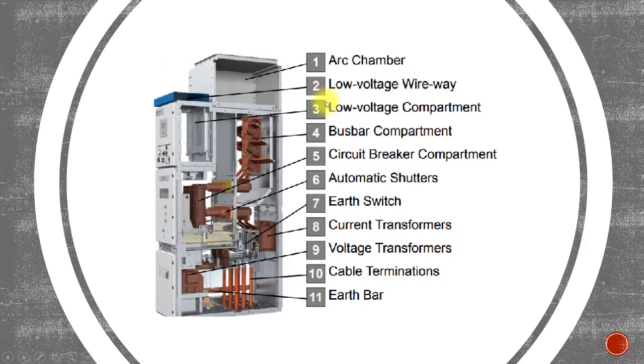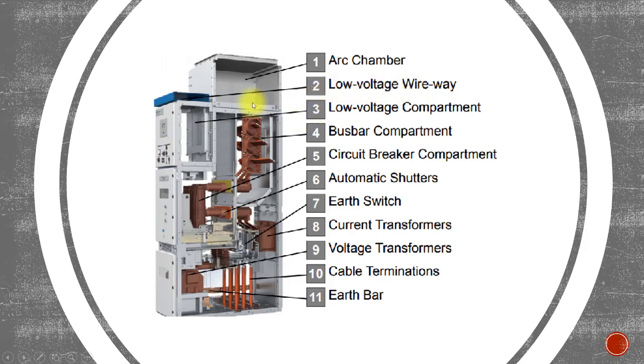The advantage of the arc chamber is that you are saving and controlling the damage to the MV switchgear in case of an arc fault. If there is no arc chamber, the complete switchgear can burn out and the adjacent chamber can also get damaged. That is why the arc chamber is found more and more in new designs. Number two is the low voltage compartment, where all the low voltage wiring, control wiring, protection wiring, and mimic control is available.